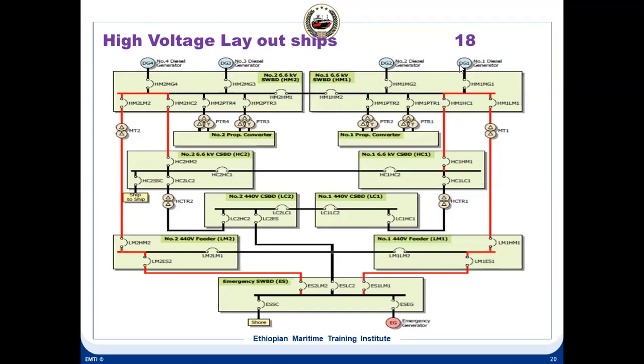So if you see here, this is high voltage equipment. This is also high voltage equipment. This is also high voltage. Now these transformers are step down transformers, high voltage to low voltage. So 6.6 kV is being stepped down to 440 volts. So this is a low voltage switchboard. This is also a low voltage switchboard. Now what about this? This is a high voltage switchboard because there is no step down. It is directly coming here at 6.6 kV. So this is high voltage.